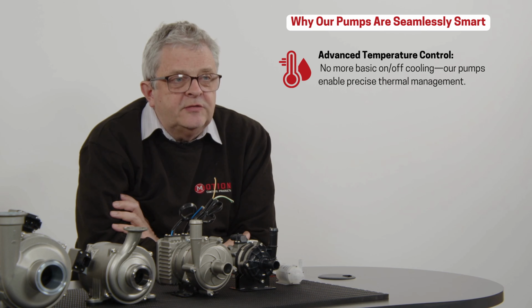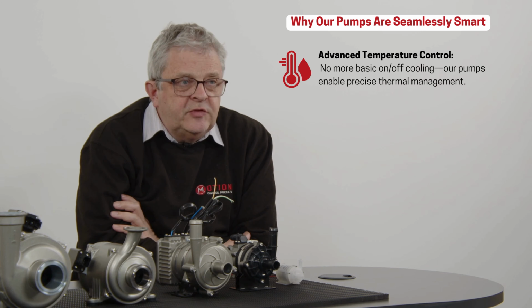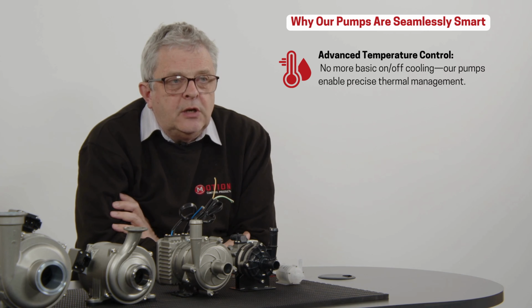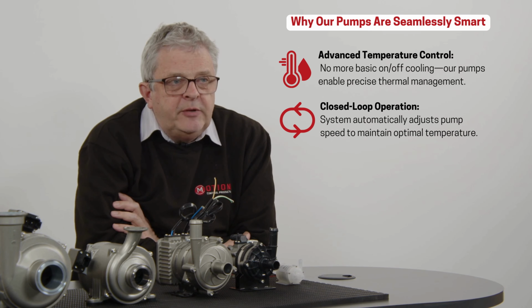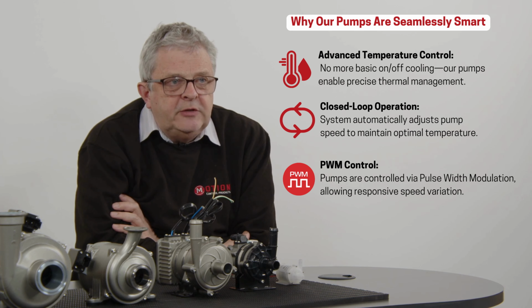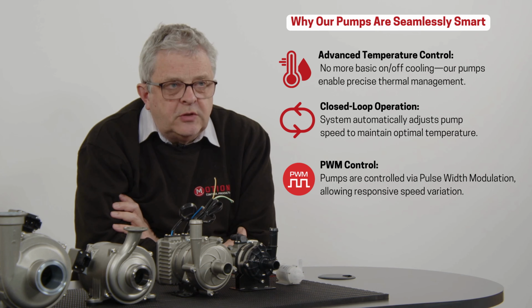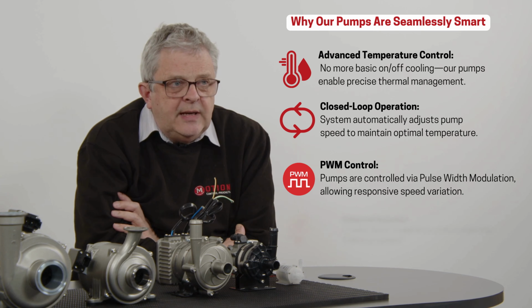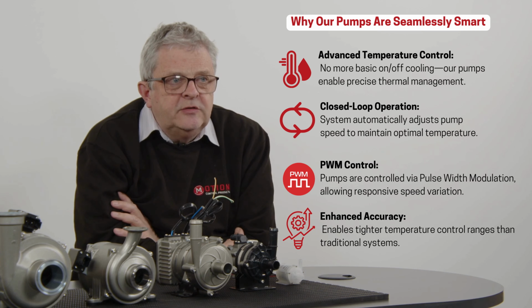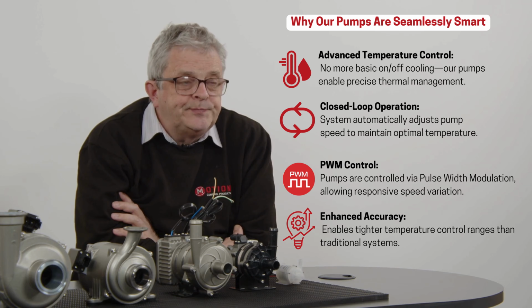Gone are the days of simple thermal management systems which switched on and off cooling. Now, closed-loop systems will vary pump speed to much more precisely control temperature. Our pumps are PWM-controlled to vary speed responsively to your control system. This allows system temperatures to be controlled within tighter ranges than ever before.